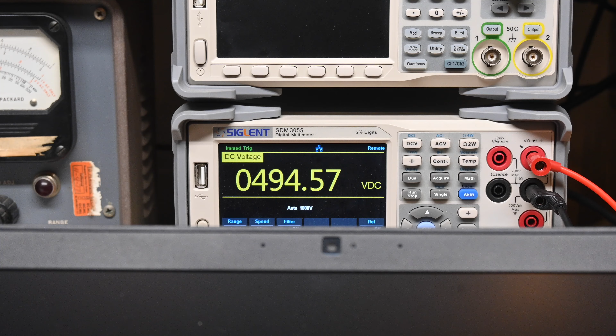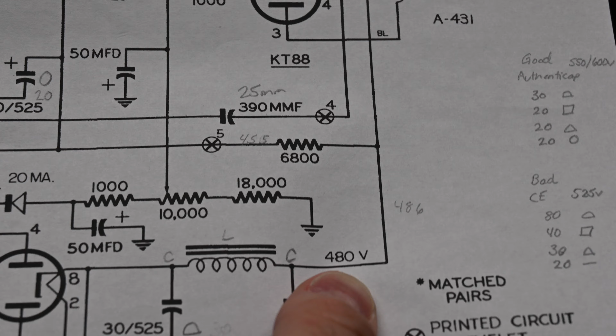And then I'm going to change the voltage on the AC power analyzer to 117. And we'll watch that drop. So we're seeing 500 volts directly off of the rectifier. And if I move that to the other side of the choke, it's measuring 494. And the specification on the schematic, as a reminder, is 480. So we're totally fine there. That won't be an issue at all.